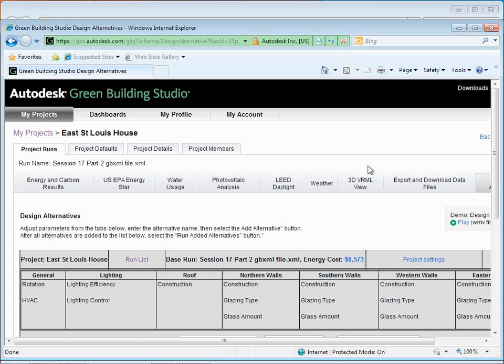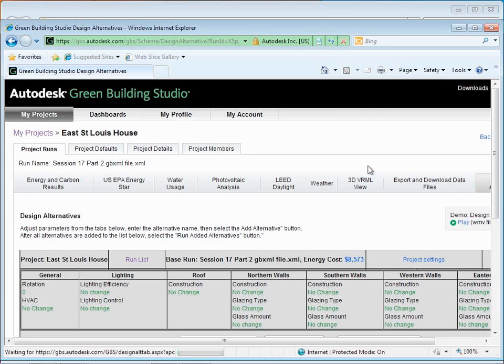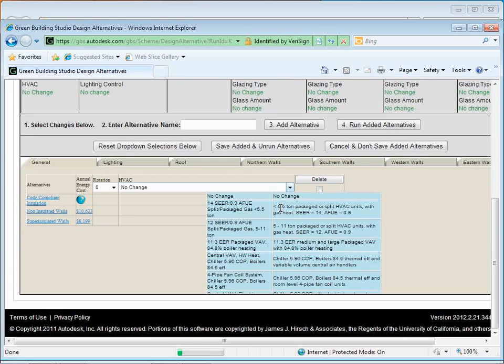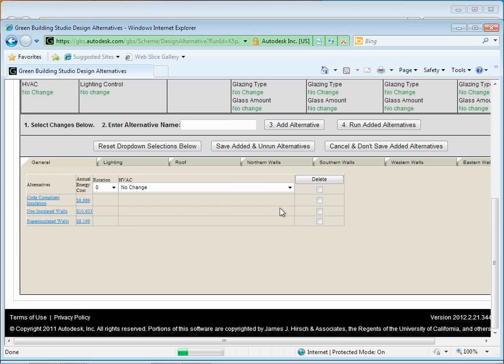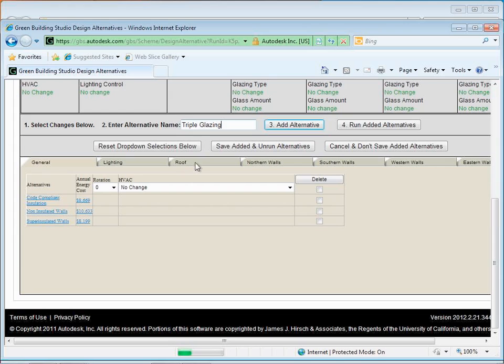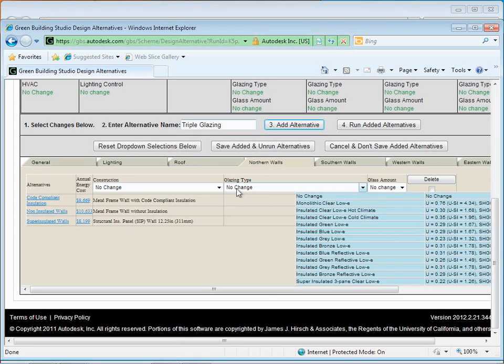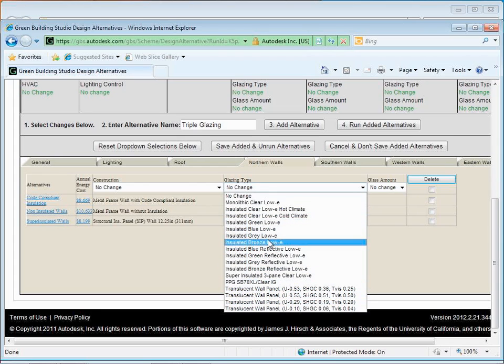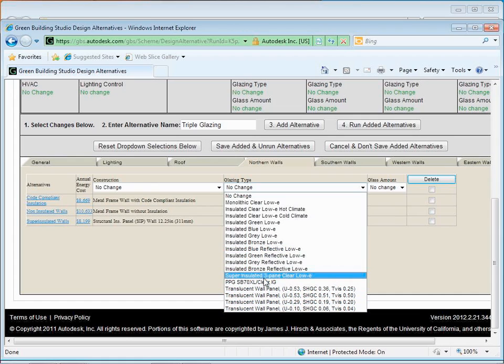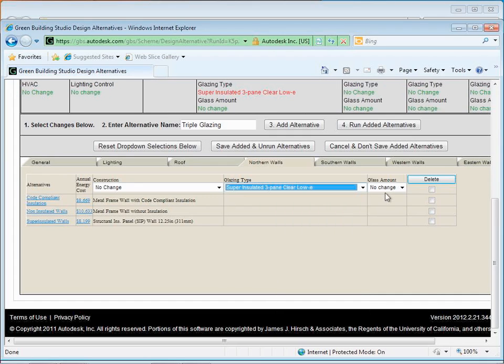Let's try glazing. Glazing is another one that's kind of a good one to start changing around. It's kind of interesting. I can see already here the super insulated walls were $8,200. The non-insulated walls were $10,600 in terms of an annual cost. Like $2,500 a year. That will actually add up to be something pretty significant. It was worth putting the insulation in the walls. Code compliant insulation was $8,669, kind of in the middle somewhere. Let's try changing some glazing alternatives. Right now, let's go ahead and let's call it, say, triple glazing. So some people like to do something like that, although I don't find it generally helps out very well. I can change it to be insulated, green. Actually, the color actually does make a difference in terms of the glass. Oh, there's super insulated, three pane, clear, low E. We'll try that.